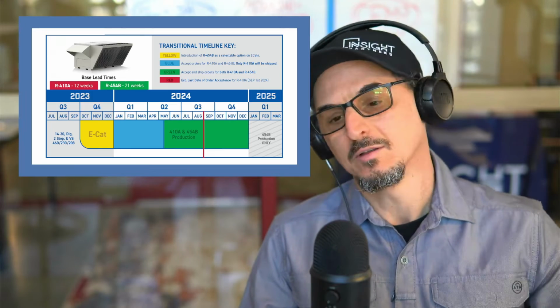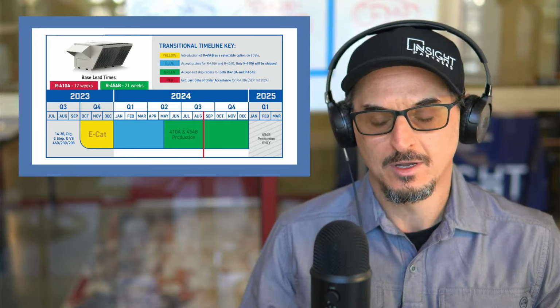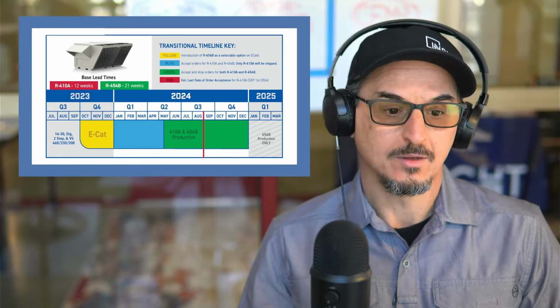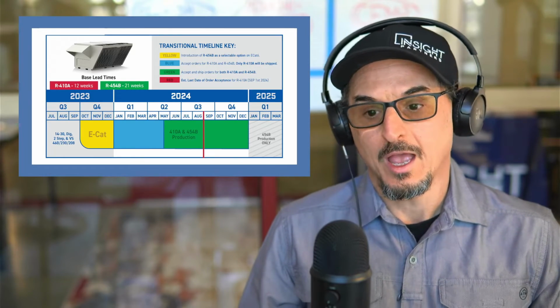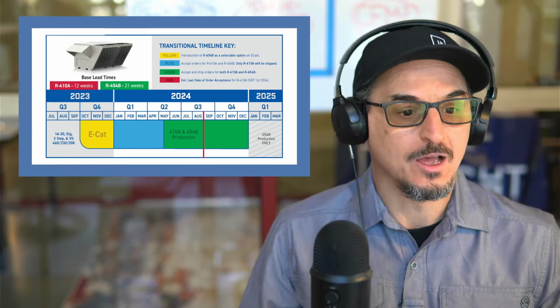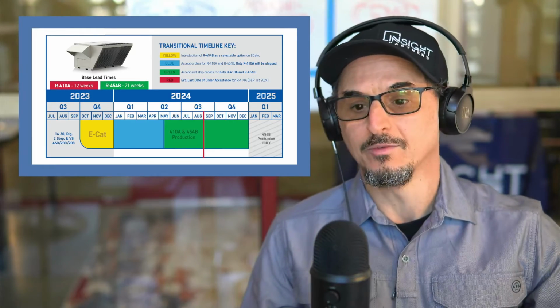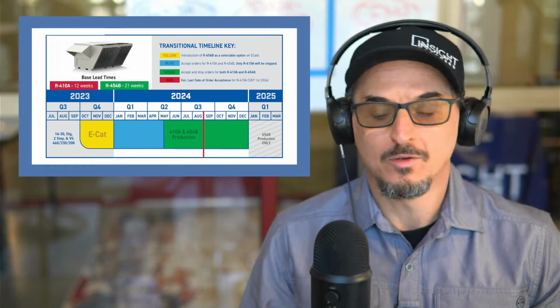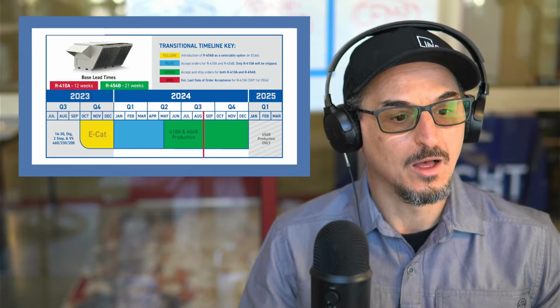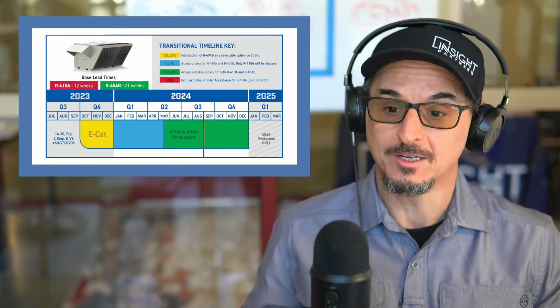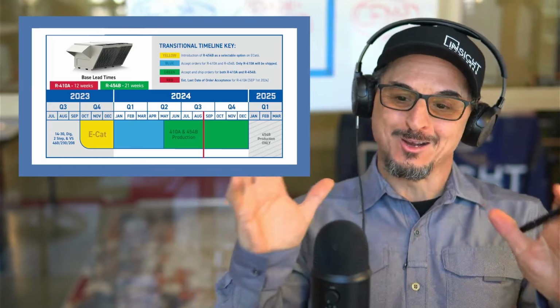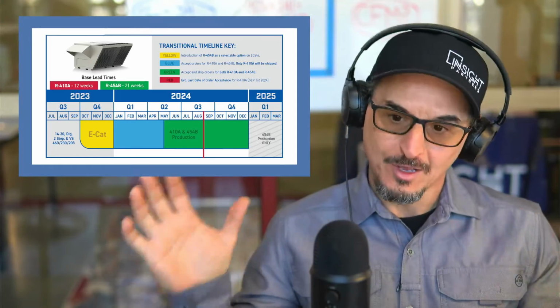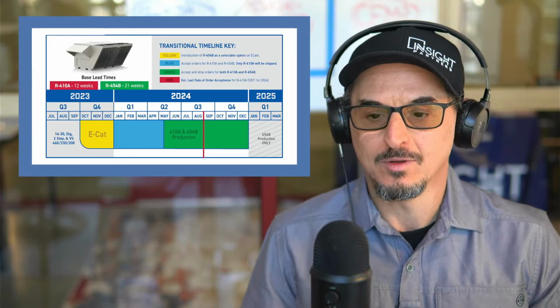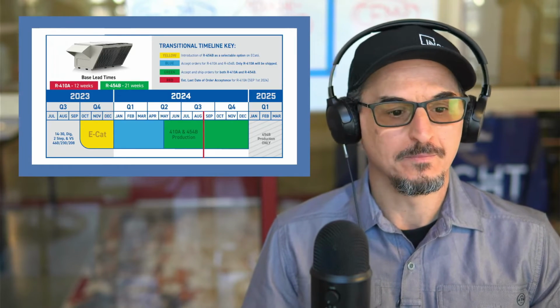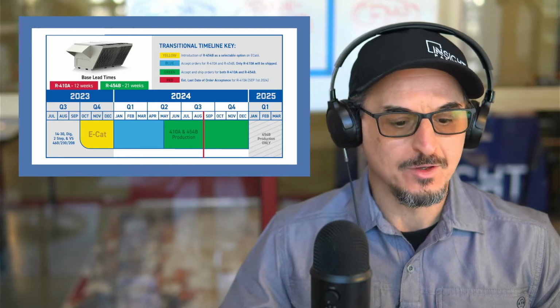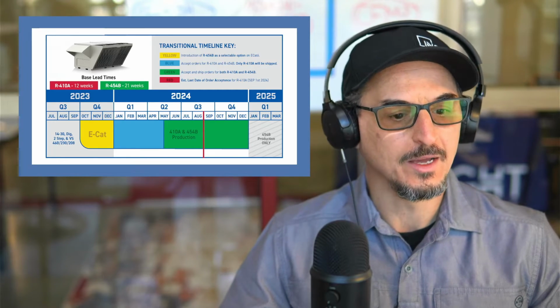End of August, for this particular manufacturer, is the last date to order 410A equipment so they can get it out by the end of the year. The other thing to be careful of is lead time - some manufacturers have, as shown here, 454B lead times of 21 weeks, and some manufacturers may have lead times of 30 weeks, even for 410A equipment. So keep that in mind. If you're specifying a job today, my engineering brain says wait, let these get out in the field and test it. But really, there's no time to do that. So I would say switch over now if you can, if it's possible - that would be my personal advice.